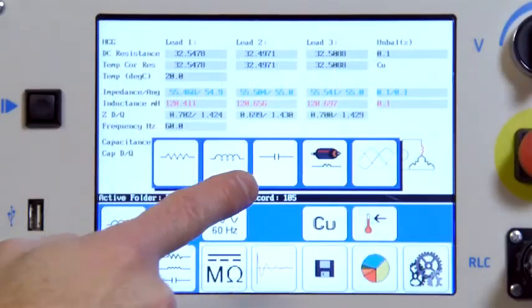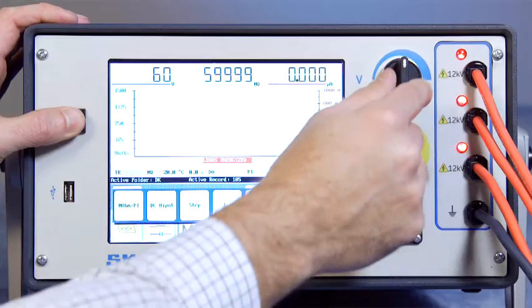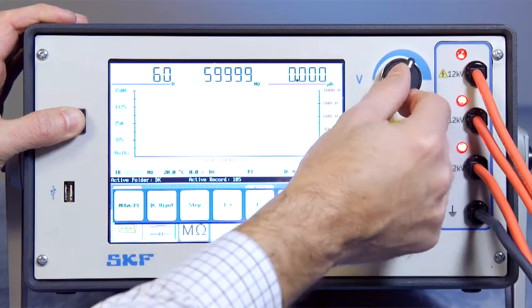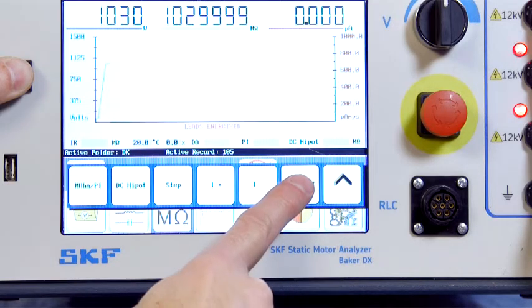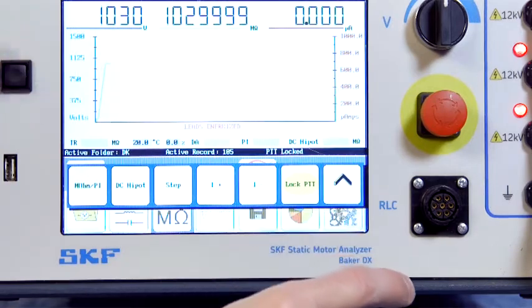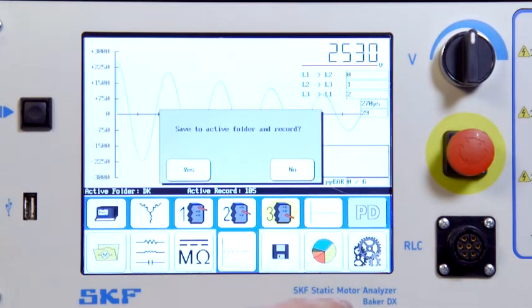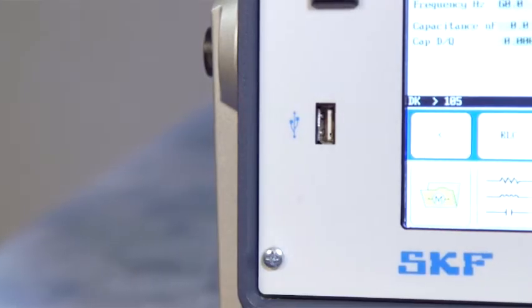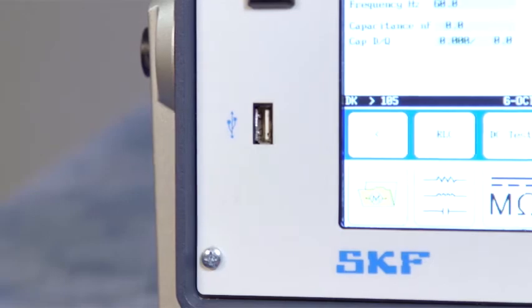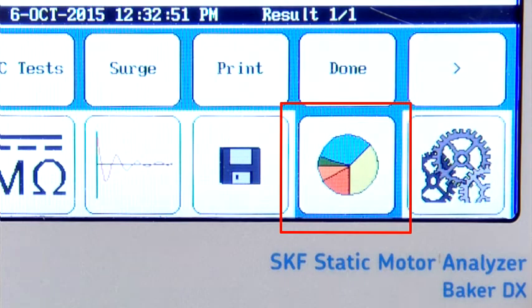To run a test, select the test type desired, select the lead if applicable, press the PTT button, and ramp the test voltage. For the long DC ground wall insulation tests, a PTT lock is available. Save test data by pressing the save file icon. Data can be exported via USB for archive and desktop report generation.